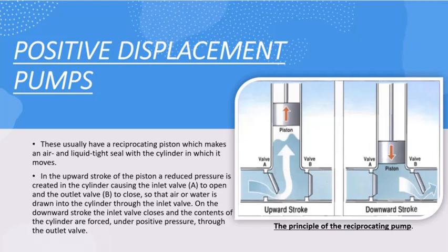First we will learn about the positive displacement pump, or the reciprocating pump. In a reciprocating pump, as you can see, there is a piston assembly which does an upward stroke and a downward stroke. In the upward stroke, it creates a low pressure region inside the cylinder area, which causes the high pressure fluid to open the NRV — or non-return valve A — and rush the fluid inside the cylinder area.